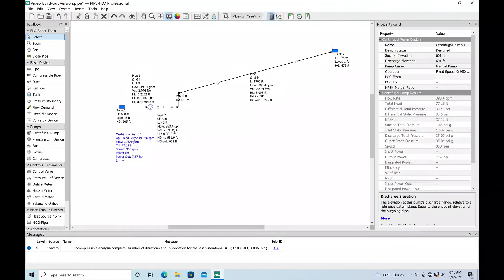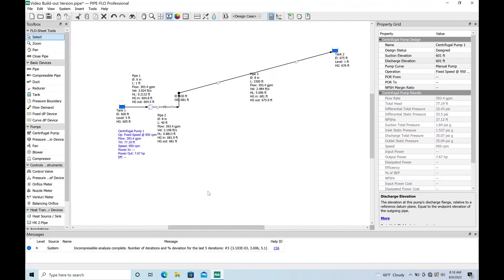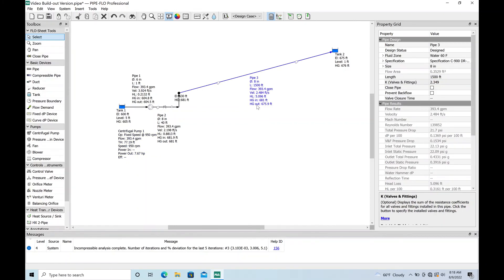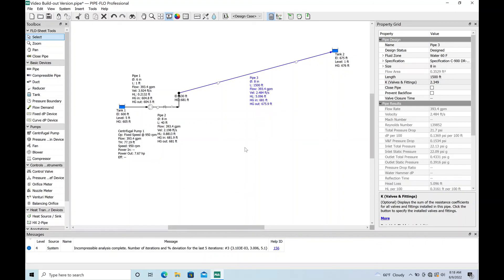Here we are, we're at the end of the road already. So quickly the pumps are running at 950 RPMs and delivering 393 gallons a minute at 77 feet. We got a pretty good velocity of two and a half feet per second in our force main so we'll do all right, we'll clear it out pretty good. We might want to bump up the velocity a little bit there.